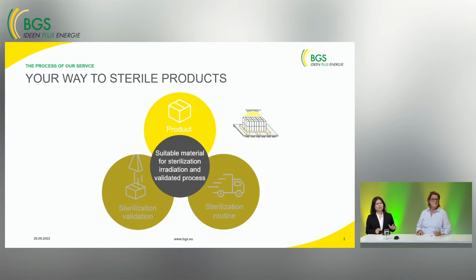The technical aspects: we've talked about the sterilization dose and maximum acceptable dose before. The third aspect that we need to clarify is the product configuration. For example, how is the density of your product? How is the product orientation in the transport box? How is the packaging scheme of your pallet? Is there any shielding component in your products, for example, metal? We need clear and transparent communication from your side, so that not only can we give you the best solution, but also a correct one.